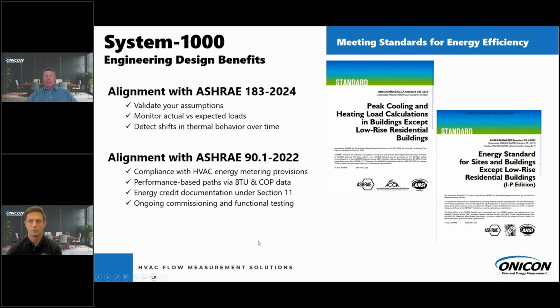A slightly older standard, but equally as important, is ASHRAE 90.1 from 2022, and that says that you have to have compliance with HVAC energy metering provisions. Well, with the System 1000, obviously we're monitoring our energy there. It asks that you have performance-based paths versus via BTU and COP data. Obviously, we've provided both of those as well. The data that you can get out of your System 1000 can help you with the documentation for your energy credits that you can get out of Section 11 of 90.1. And then lastly, 90.1 asks that you do ongoing commissioning and functional testing. With all the information that comes off of a System 1000 regarding your system, it's an easy way to demonstrate that ongoing commissioning and functional testing.